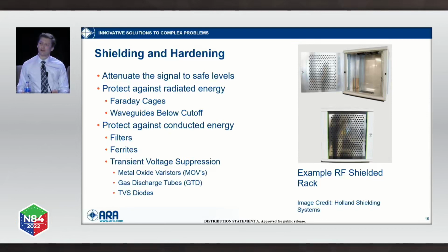I've also seen the case where there was a bank putting together a server room and they wanted to shield it. And they were talking to my team to see if the shield was going to be effective. I asked what the shielded material was made out of. They said they'd get back to me, and the next week they sent me in the mail a sample of the material that they had cut right out of their shield. And so it doesn't matter what it's made out of. There's a huge hole in your shield. I can promise you it's not working.